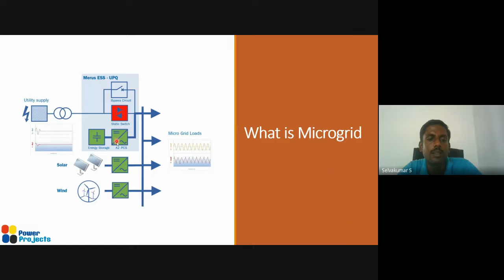Fault current is another big challenge you need to look at. When you have synchronous machines, the fault current will be 6 times, 8 times the rated current, etc. This fault current helps you to have better protection, discrimination and so on. But in a scenario of purely renewable based grids, it's all power electronics. The short circuit current is almost close to the full load current, and you will not be able to differentiate whether this is a fault or normal operating condition using the current reduction principle. So the biggest challenge in renewable integration is effective protection, and what we can look at is that these VSC based converters can probably contribute higher short circuit currents and give better coordination.